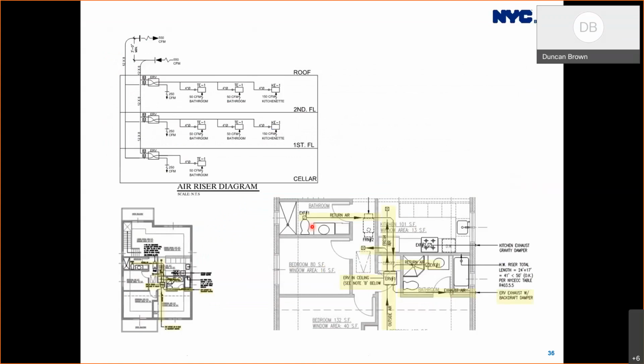Next slide, please. So how might you typically document compliance? Well, here's a very schematic example of what might represent good documentation. First, on the top left there's a riser diagram with the ERV clearly shown. And then in the small plan, there's a ductwork schematic where the ERV and there's a blow up can clearly be seen. And of course, there's an equipment schedule with the ERV or HRV clearly specified. It helps if you can clearly identify that on your drawings when you put that in your schedule. Sometimes it won't be clear from a manufacturer's name or spec that it is in fact an ERV or an HRV. Next slide, please.